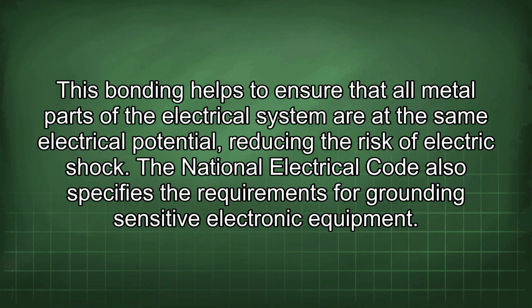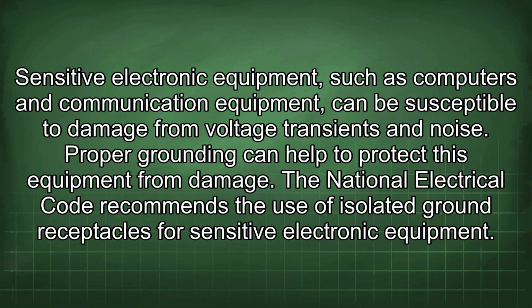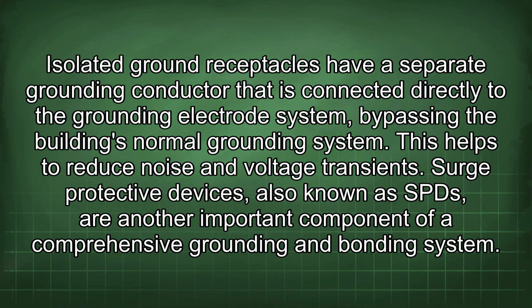The National Electrical Code also specifies the requirements for grounding sensitive electronic equipment. Sensitive electronic equipment, such as computers and communication equipment, can be susceptible to damage from voltage transients and noise. Proper grounding can help to protect this equipment from damage. The National Electrical Code recommends the use of isolated ground receptacles for sensitive electronic equipment. Isolated ground receptacles have a separate grounding conductor that is connected directly to the grounding electrode system, bypassing the building's normal grounding system. This helps to reduce noise and voltage transients.